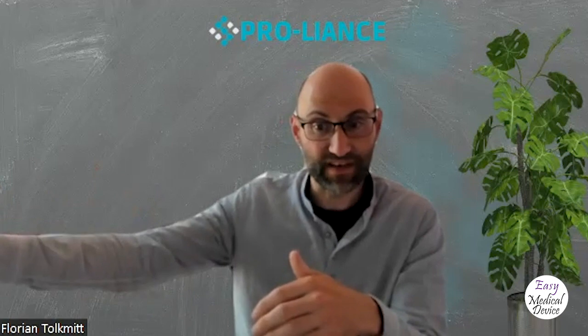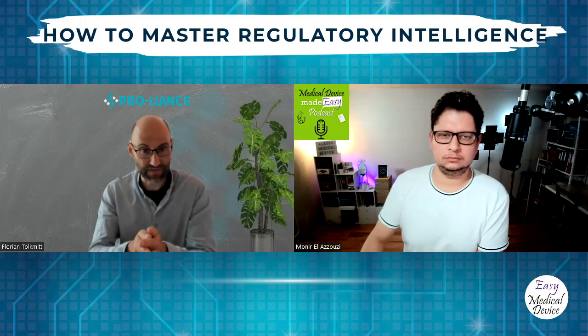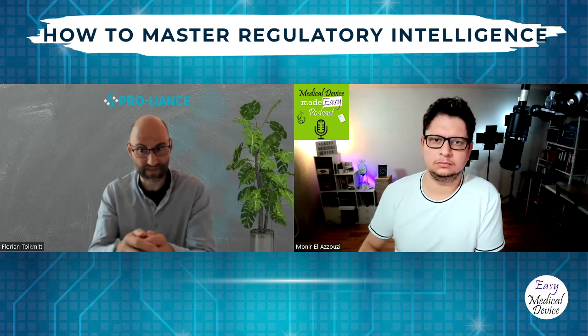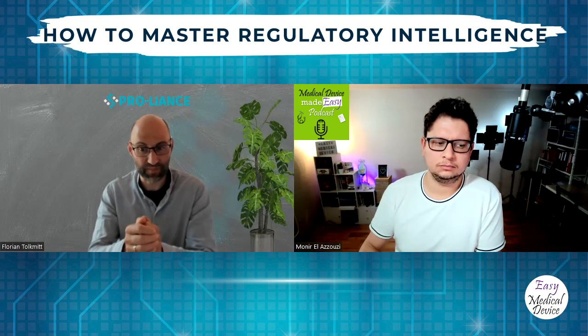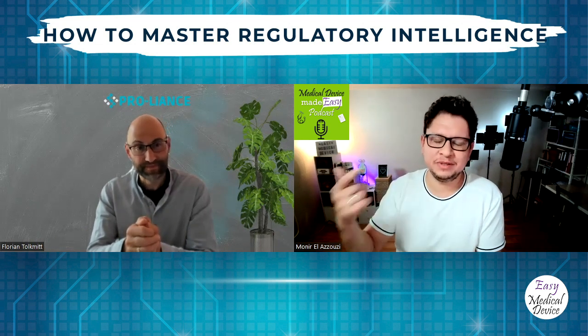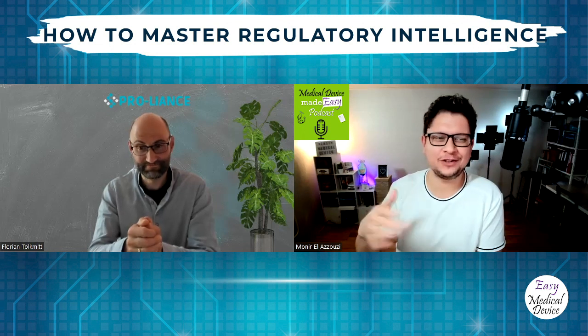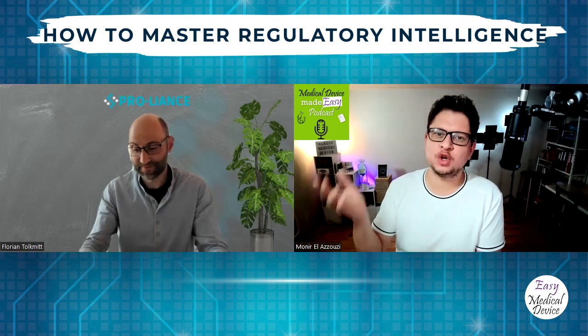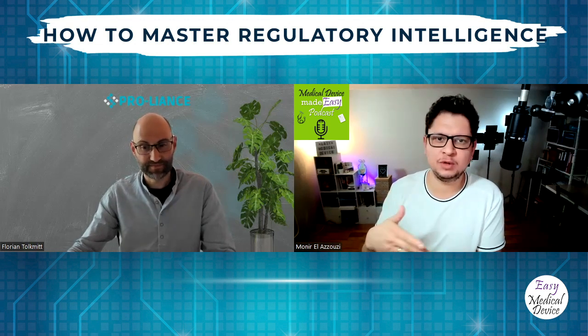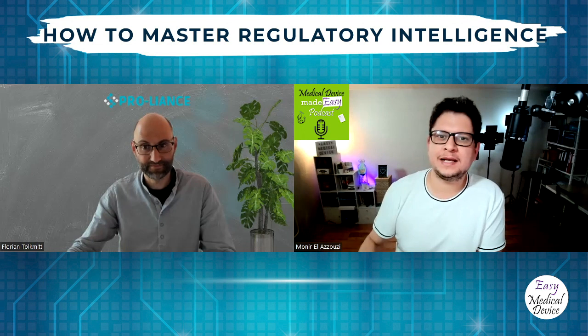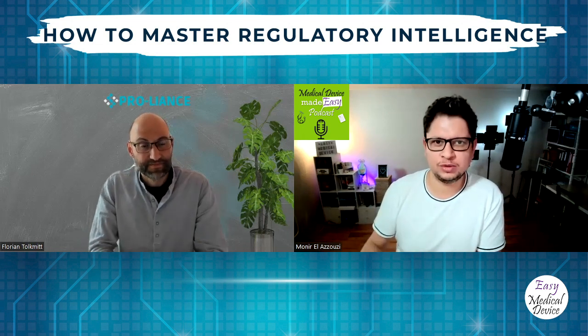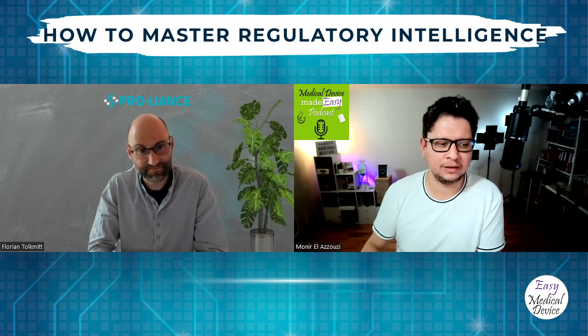Exactly. And even if you have closed all gaps and the submission date is still maybe a few months or a year ahead, don't forget to keep updating your technical documentation, because it's a living thing. It's not something that you do once and then leave alone forever. So keep on updating it, and even after submission, you need to keep it updated always. Under MDD, we had a lot of technical files that stayed the same. But now there are so many documents inside that should be updated, like clinical evaluation, post-market surveillance, etc. They should be inside your technical file. So if there are any changes to the documents, you again have to update your technical file. So it's important there. Right.